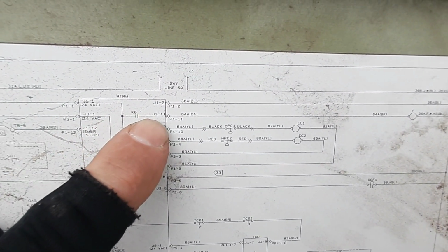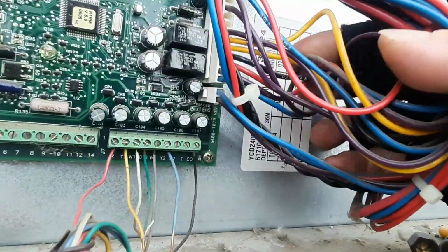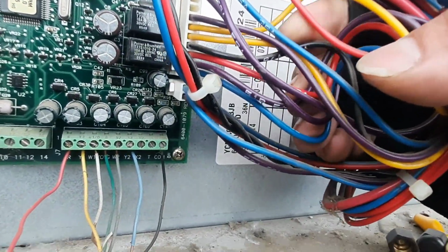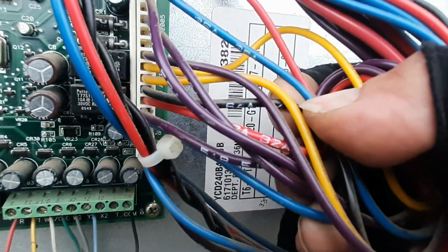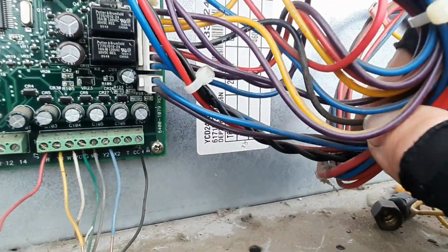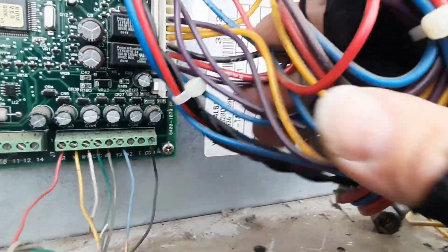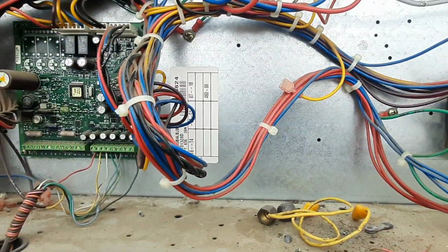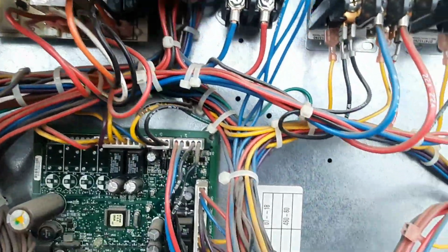So if we look at our diagram, F is going to show us the indoor fan contactor. This side here is going to be common, and we can see J1 pin 11 is going to be 64A black. There's my J1. If we count down 11, it's going to be that one there, 64A. So I need to get my meter on there and see if it's putting voltage out. It obviously is periodically. It's got to be one of these relays on the board because it comes straight from that board. There's nothing else in between, and it's that wire there.